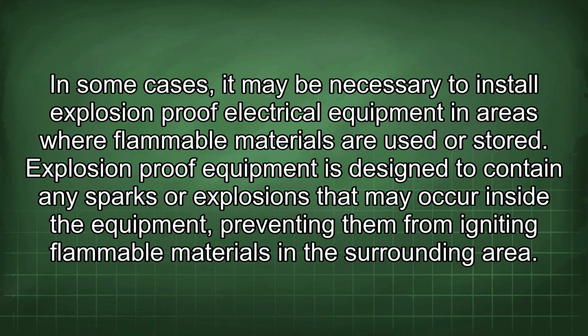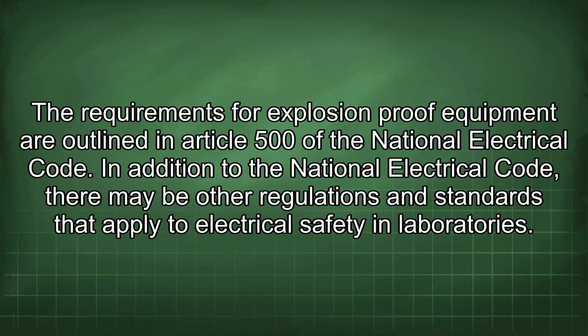In some cases, it may be necessary to install explosion-proof electrical equipment in areas where flammable materials are used or stored. Explosion-proof equipment is designed to contain any sparks or explosions that may occur inside the equipment, preventing them from igniting flammable materials in the surrounding area. The requirements for explosion-proof equipment are outlined in Article 500 of the National Electrical Code.